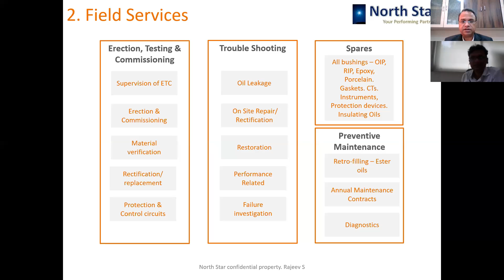Then we do preventive maintenance, also called retrofilling, which is coming up in a big way, where old transformers can be revitalized by replacing their insulating liquid from mineral oil to ester oil. This enhances the life of the transformer by another 5 to 10 years, depending on the transformer's condition. We also do annual maintenance contracts and help clients diagnose various issues they face on site with their transformers.